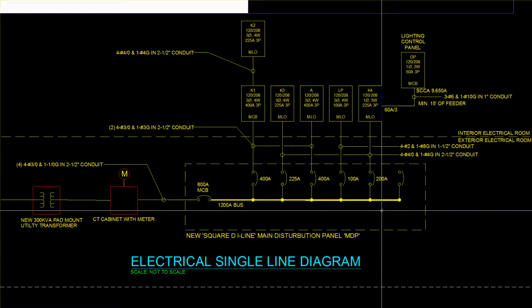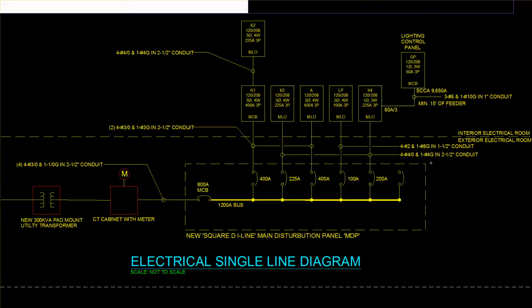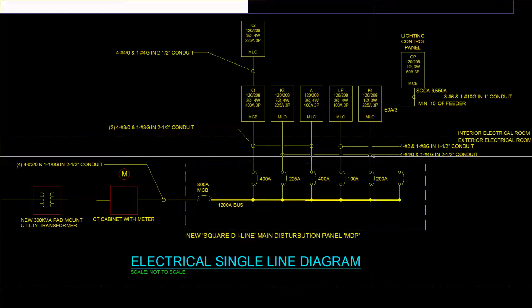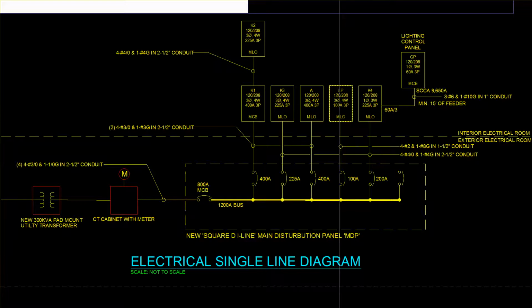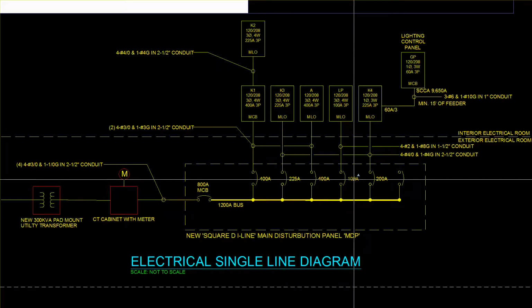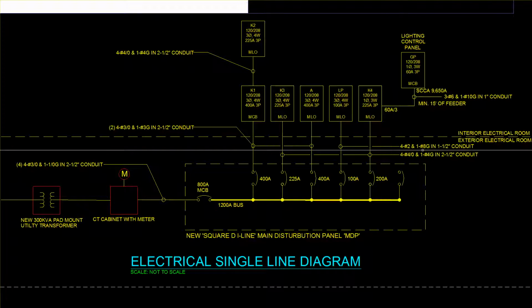Extra points if you caught that. But then you'll see these different callouts here: 4 4/0, 1 number 4, 2.5-inch conduit. And so these are called out for the 225 panels here. And then we have a 100 amp panel here, panel LP, and it's fed with a 100 amp circuit breaker, and it has 4 number 2s with 1 number 8 ground and 1.5-inch conduit.